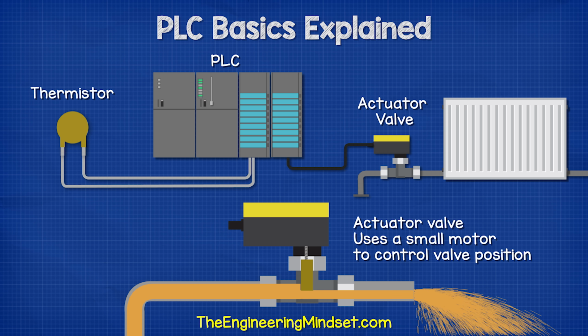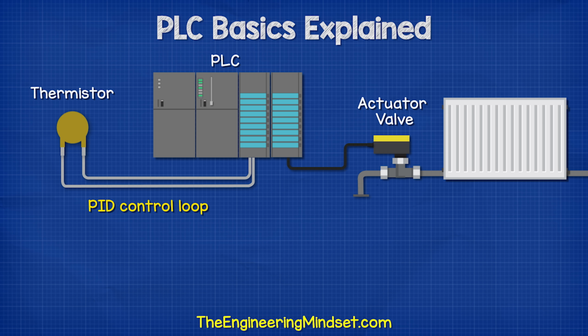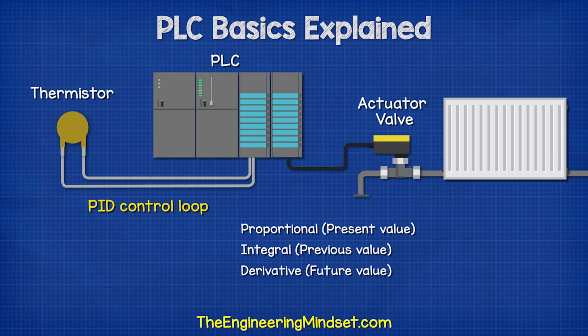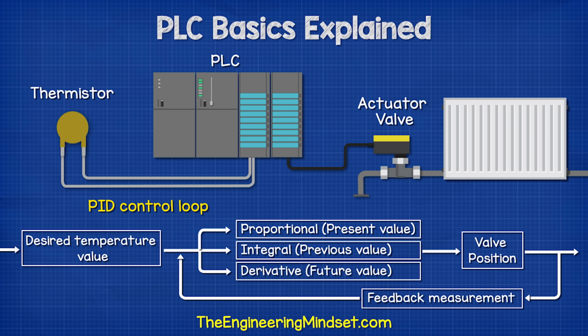the room. For this, we would use a PID control loop, which stands for Proportional, Integral and Derivative Control. We won't go into too much detail on PIDs, but essentially this will control the valve position to ensure it only opens enough to suit the difference between the room's desired temperature and the room's actual temperature.